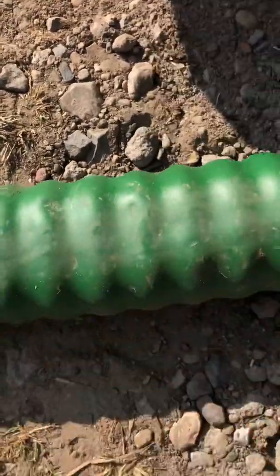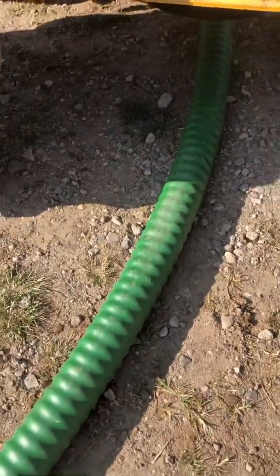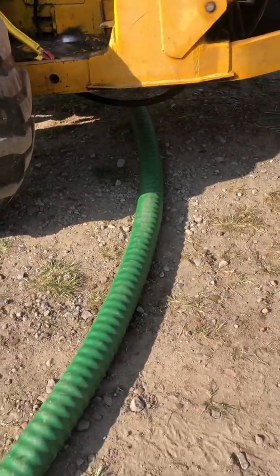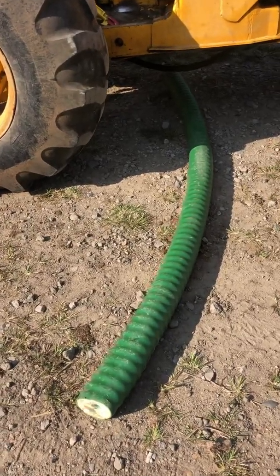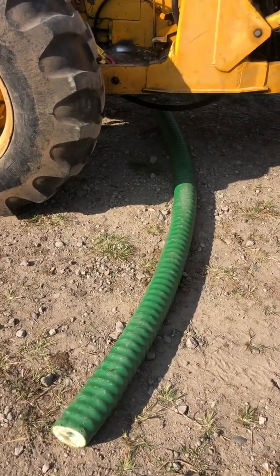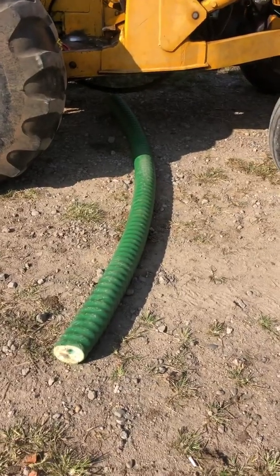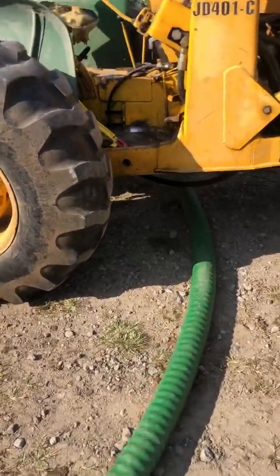Just ever so slight dent there. You notice it's in the gravel — you're not going to be able to make a pipe that will stand that. If you want to do it right the first time, go with the foam underground pipe, whether it be Logstor, Thermopex, Rehau, or Heat Master — they have their own brand too. Like the Fabulous Thunderbirds song goes: this stuff is tough enough.